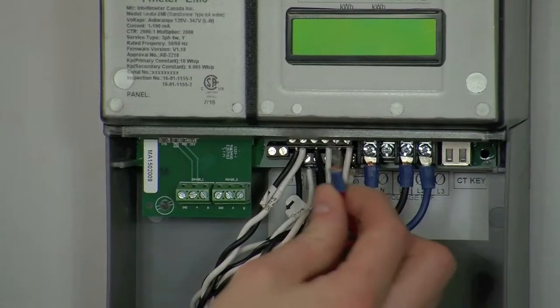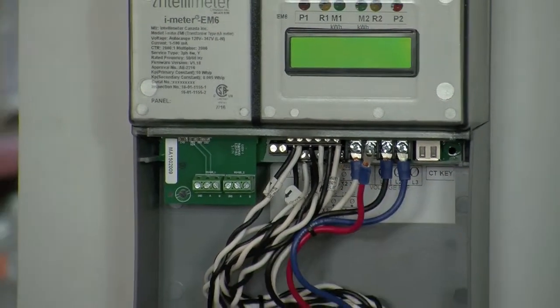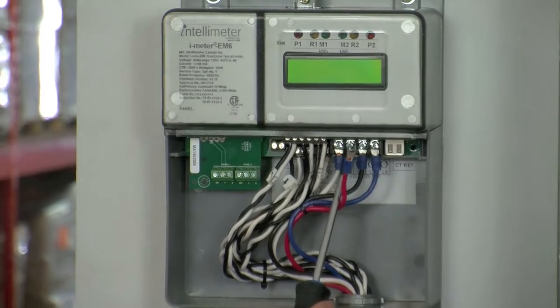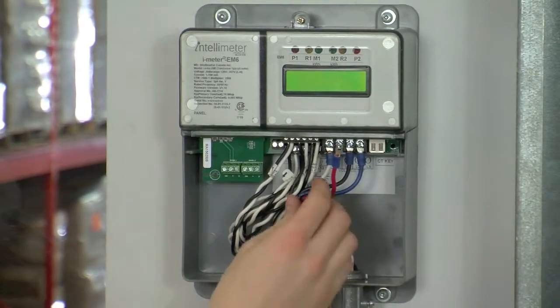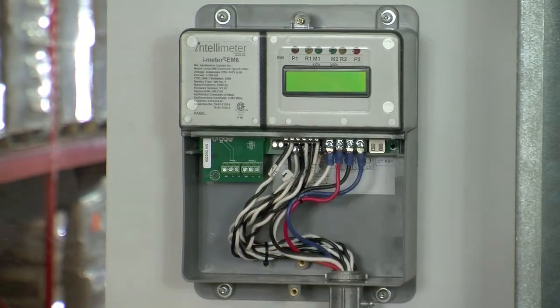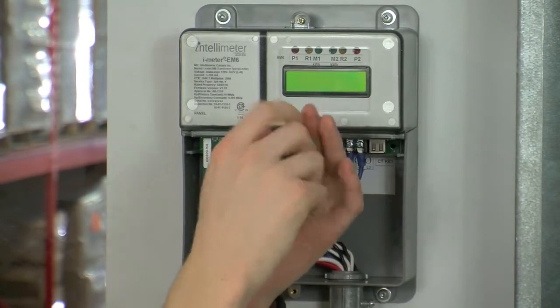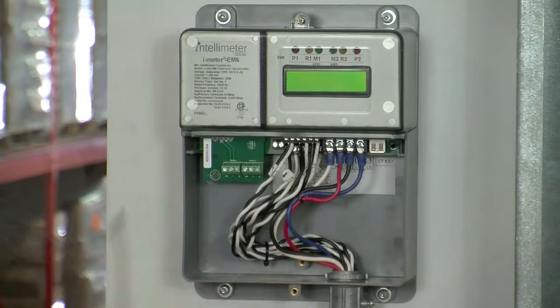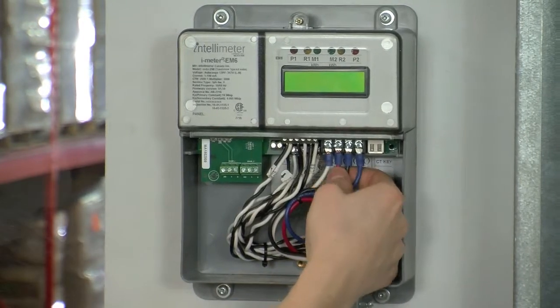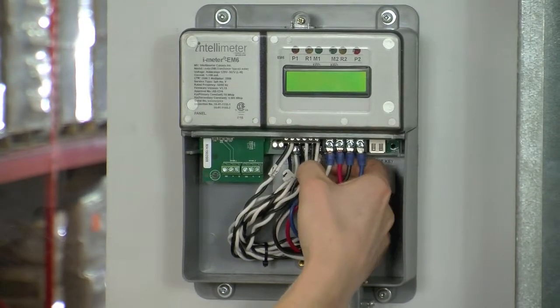Use fork connectors for the reference voltage. Be careful not to over loosen the terminal screws as they may fall out. You can then gently pull on each wire to make sure that they're all firmly seated inside the terminals.